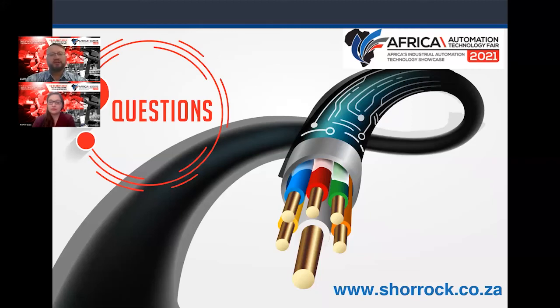Power boost, on the other hand, is for DC motor applications, where we have a small inrush current that we need to maintain. So the motor starts up and it usually runs at, let's say it's one motor on a 40 amp device. The device would start up and run at 38 amps, which is perfect for the power supply. It can handle that. But there's a small inrush current when it needs to get into movement, and that inrush current could be 60 or 70 amps. For that, we allow up to 150% of the full load current of the power supply for 5 seconds. And only after that, it will shut it down.